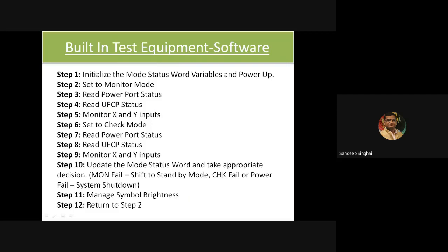In case of built-in test equipment, this is the algorithm which we follow, which continuously monitors the various power supplies and the various signals. In case there is a signal failure from the mission computer end, so input XY signals are not coming, we have to ensure two things: one, to protect the phosphor of the CRT from burning, and number two, to switch into the electronic standby mode, which will provide some help to the pilot.